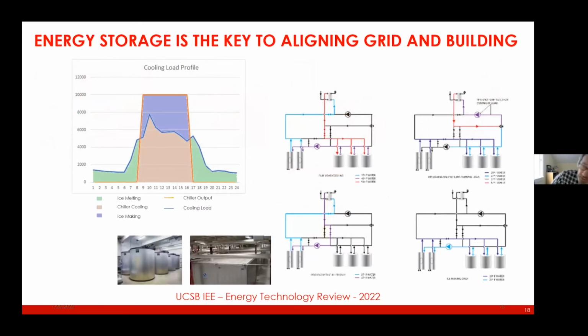So energy storage is the key to aligning the grid and the building. Obviously, behavioral change is one characteristic, but as we saw, looking at the thermal balance of the building, behavioral change isn't going to get you past that problem, and you need thermal storage. So here we have a flow diagram for an ice making system, and some images of some ice making systems that I was involved with in the past.